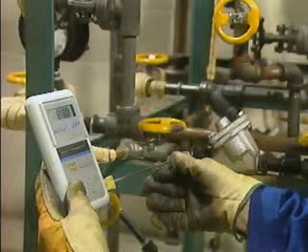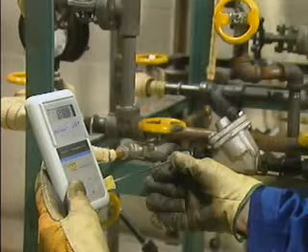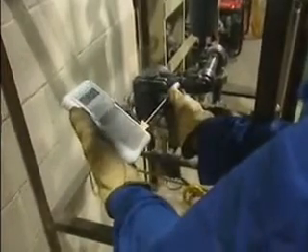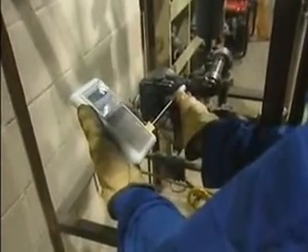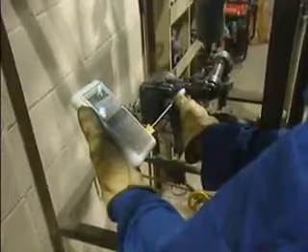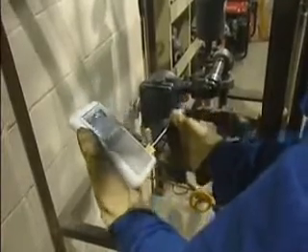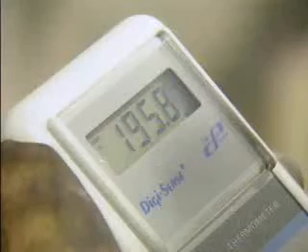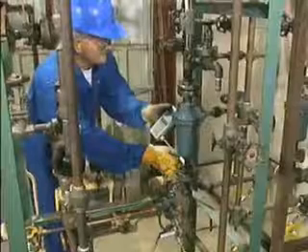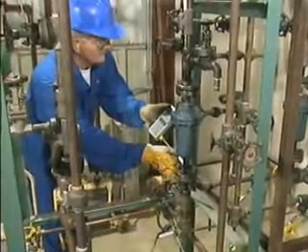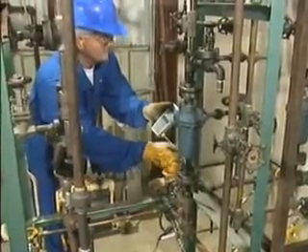For example, a properly functioning steam trap is usually warm because live steam is unable to escape from the trap, while a cold trap is probably not working. However, a trap normally operates somewhat cooler when it's working properly than when certain malfunctions occur. For instance, a significant increase in the temperature of the trap could indicate that the trap has failed open and live steam is escaping. If the trap inlet temperature is in the allowable range, trap inlet conditions are normal.